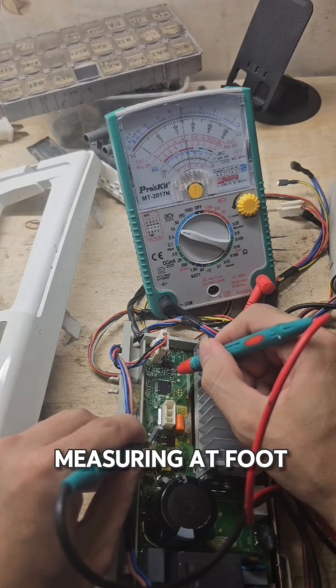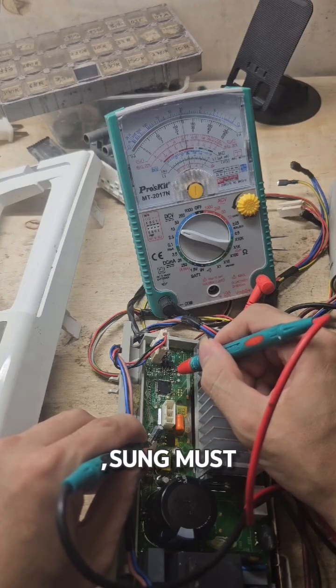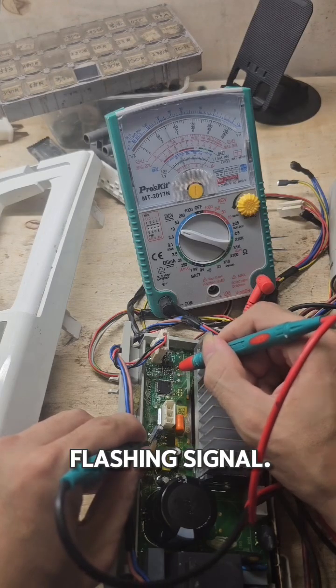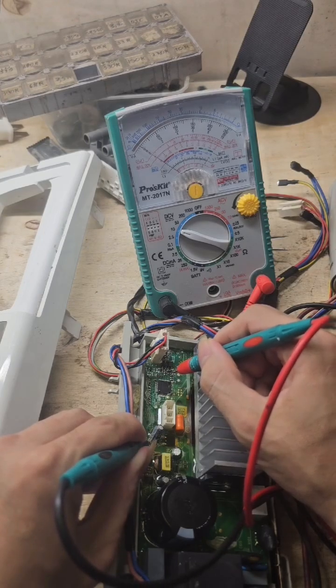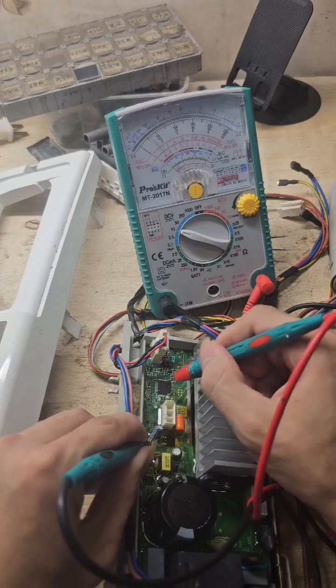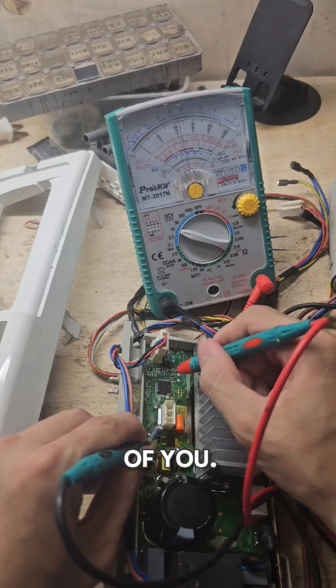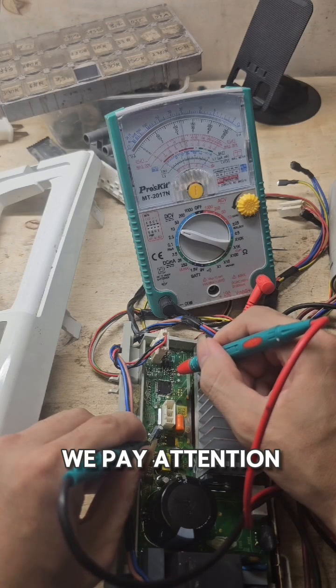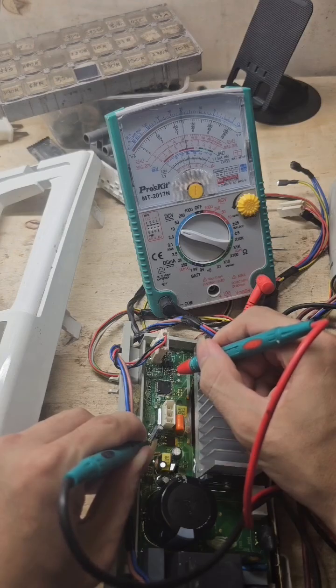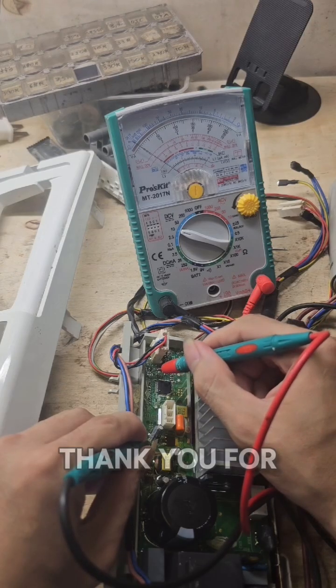So now I'm measuring at leg 2 of the emitting optocoupler. There's got to be this flashing signal. Leg 1 to this, see the meter. It's circling around 1V, guys. And now the machine is out of the SC error. When the machine fails, we pay attention to this LED on the board. It won't flicker at all. Thank you for following us.